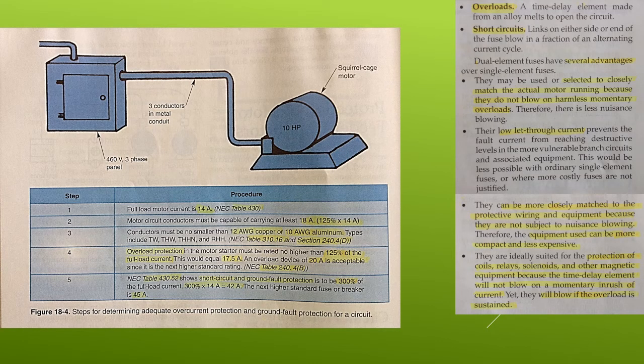Circuit protection. Protection for a motor circuit is provided by an overload relay within the motor starter and with an adequate fuse or circuit breaker at the panel. The overload protection in the starter must have a rating that is not more than 125% of the motor's full load current. Fusing or circuit breaker requirements are found in section 430.52 of the NEC.